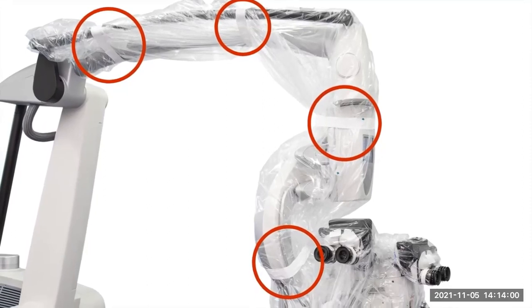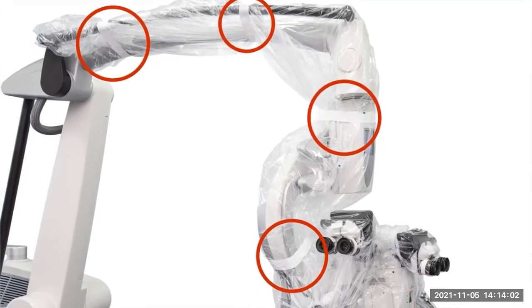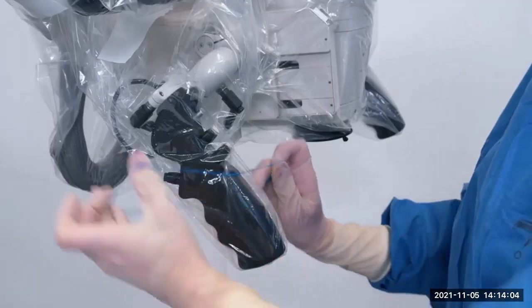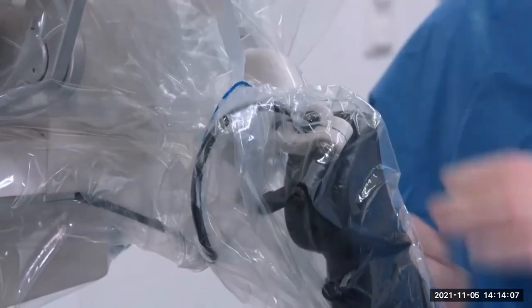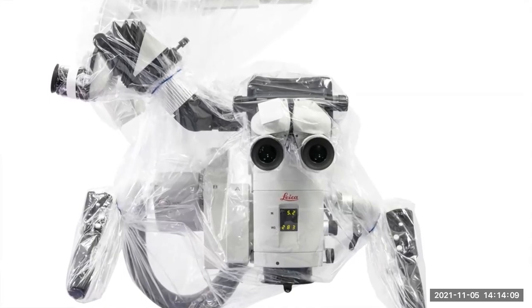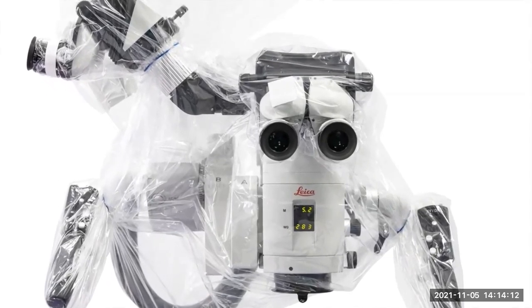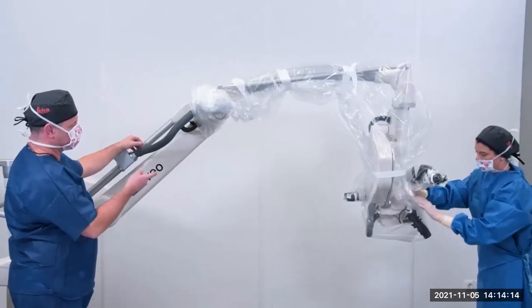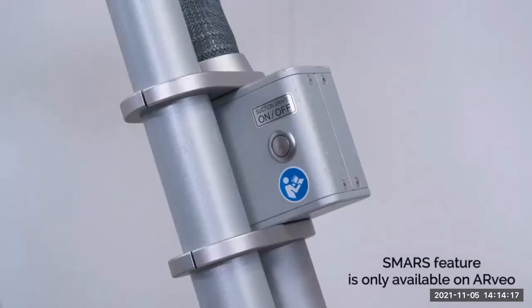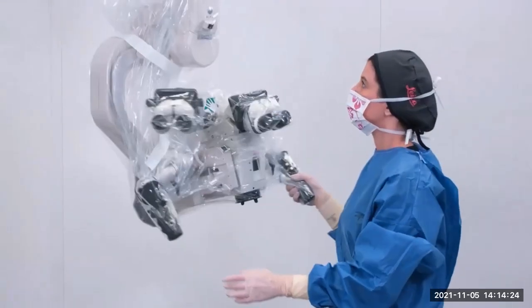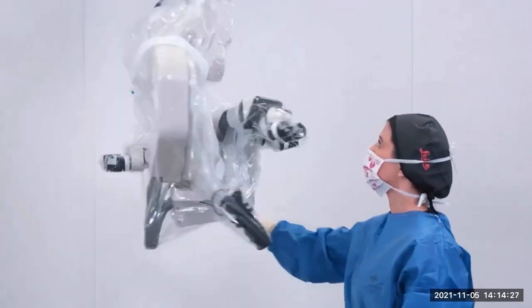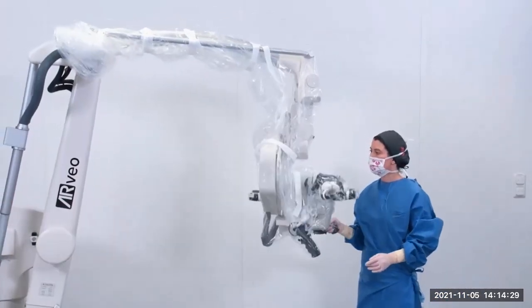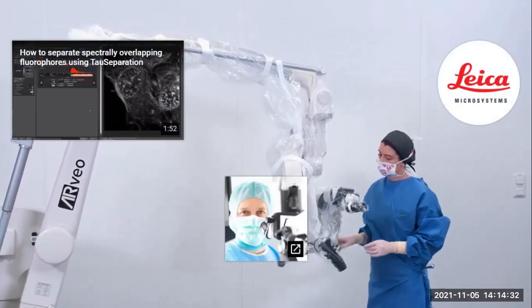Choose the option that best suits your surgical practice. If necessary, the rubber bands can be used to keep the drape tighter to the handles and the main surgeon and assistant binocular tubes. If your microscope is equipped with SMARS, the circulating nurse will press the SMARS button. This will activate the pump to extract the air from under the drape. Rotate the microscope to ensure that it can be moved easily in all directions. The drape shouldn't interfere with microscope movement. You are now ready to work with the Leica microscope.